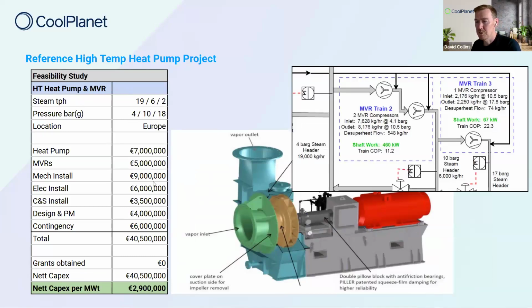What you're looking for here is a source of prime heat on the site, such as a large cooling network or cooling water towers used for part of the process. Can you intercept that heat, bring it through a low grade temperature heat pump system, and then boost it up using mechanical vapor recompression? We've done a couple of these studies.